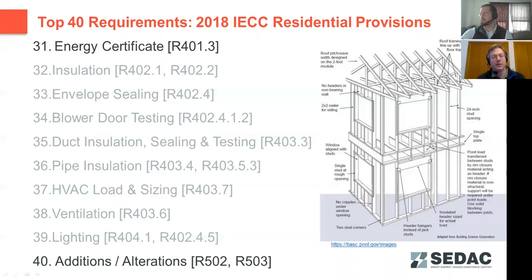And it's very similar for the HVAC system. For each component of the system, there's going to be a functionality test, essentially, that's going to verify that system's working properly. And so that plan gets developed, and that plan needs to be presented somehow to the authority having jurisdiction, so that they can verify that these systems are going to be tested and verified to be working properly.